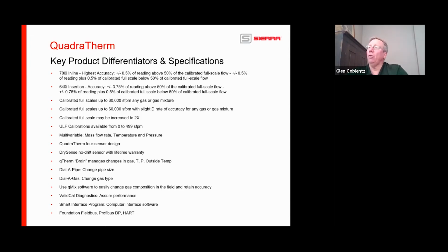But again, remember, every order that gets sent in needs a complete and correct ADS sheet. To calibrate, or even to quote the meter, you probably have this information, or at least you know it. You're definitely going to need it to send the order in so John and Fred can check it. If it's not complete and correct, you're going to be getting it back. But at least in an instance like this, where a mistake made it all the way through to the field, you get this 2x capability. I end up using this a ton in oil and gas because they'll order something for 5 million standard cubic feet per day, and the flare is 150 foot tall and the meter is railed out.